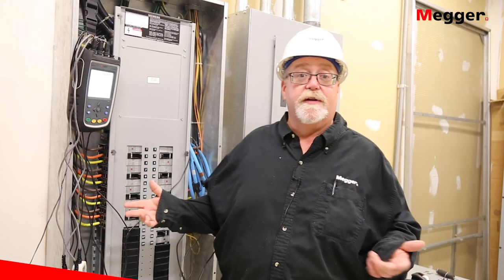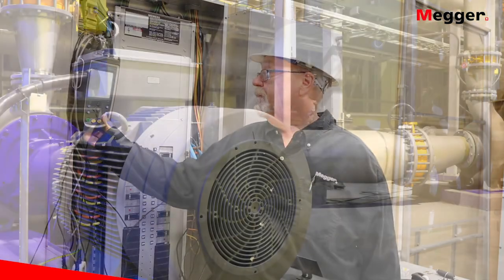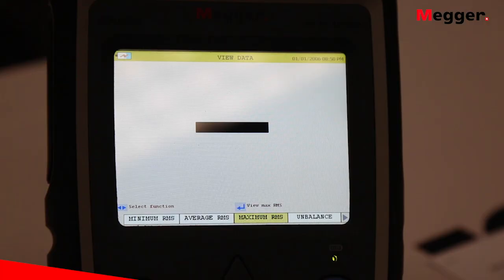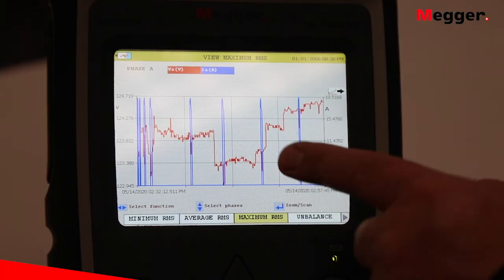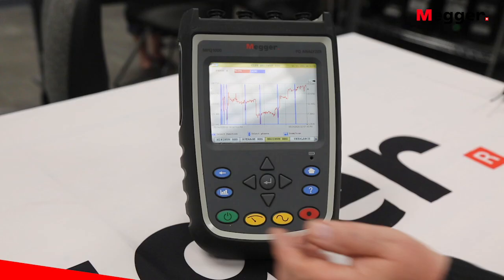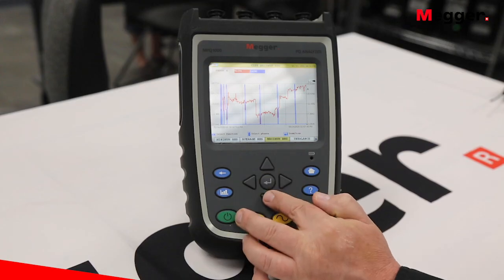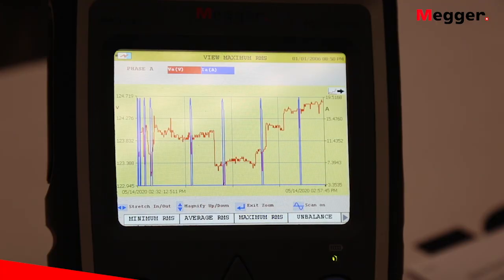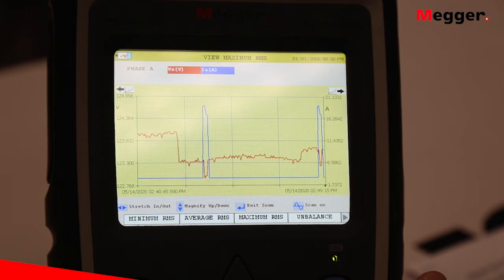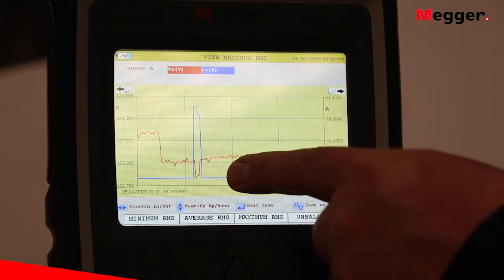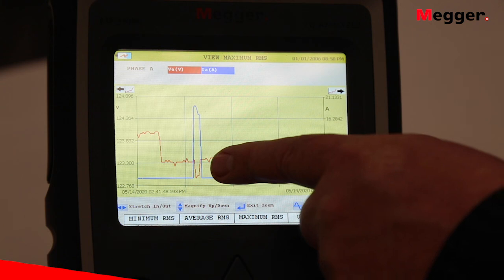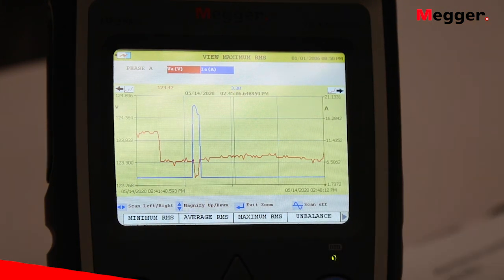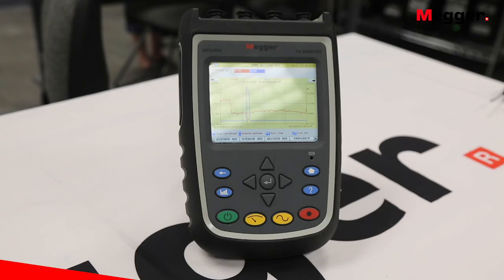And now that the recording is done, we can examine the data. Now let's look at the RMS. Now we can clearly see all the motor turn-on cycles, and now we can also zoom into this. And now, when we zoom in, we can clearly see the voltage dip that's associated with this inrush. And we can pull up a scan line, and we can actually see the values associated with them. So now let's go look at the actual inrush waveform that was triggered by this turn-on.